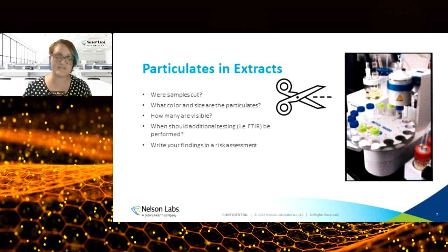I had a sponsor that had particulates in testing. They sent them for FTIR testing, and the highest match was wall spackling. That's not what you want to see in a medical device. So give us something to compare it to, just to make sure that we can actually bring it back to the device or not, and see where that investigation takes you. And regardless of what your investigation entails, you should document everything in a risk assessment that identifies what route you took to identify where those particulates are coming from, and whether it's an actual risk to the patient in clinical use.